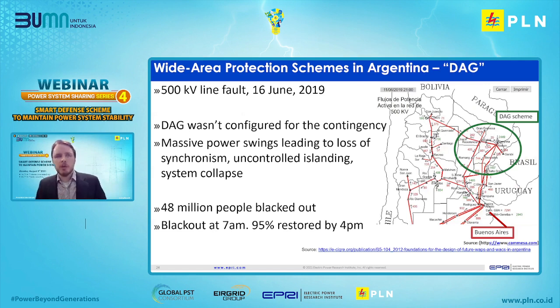So in Argentina in 2019, there was a scenario where some lines were out of service for maintenance, and there was a lightning storm and a line tripped. Now, for this specific contingency, their special protection scheme should have operated to reduce generators in the north of the country. Again, you can see here in the north there are lots of hydro plants, and in the south are the main load centers. However, the special protection scheme failed to operate, and this resulted in the power having to travel up to 1,000 kilometers in a very long route to get to the main load centers. This resulted in power swings, resulting in loss of synchronism and uncontrolled islanding and system collapse. Ultimately, 48 million people were blacked out, and they were restored later that day.